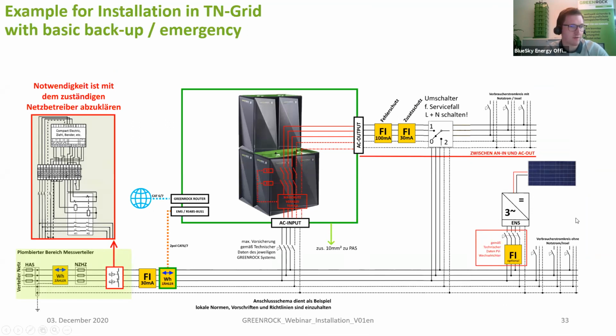We will send 3 kilowatts to this line and would go into direction of the grid. But what you can see here is an additional energy meter. This is always provided with the system. So with the GreenRock system also comes an energy meter, which is connected to the controlling, so to the energy management system. And as soon as this energy meter is sending some data, the battery is charging or discharging. So in this case, it would just charge with 3 kilowatts so that this point stays at 0, which means no energy is going into the grid or is coming from the grid. So that's the main purpose.